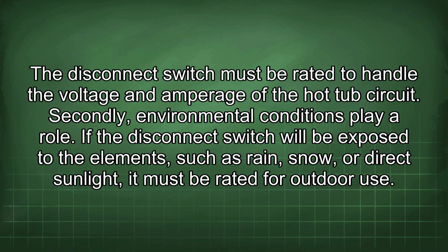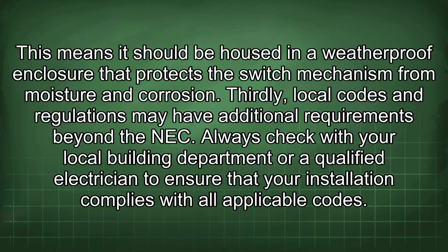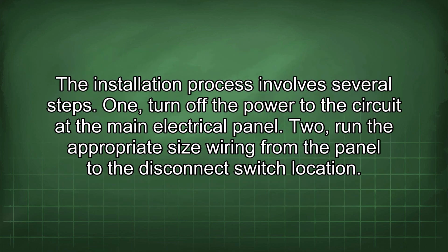Secondly, environmental conditions play a role. If the disconnect switch will be exposed to the elements such as rain, snow, or direct sunlight, it must be rated for outdoor use. This means it should be housed in a weatherproof enclosure that protects the switch mechanism from moisture and corrosion. Thirdly, local codes and regulations may have additional requirements beyond the NEC. Always check with your local building department or a qualified electrician to ensure that your installation complies with all applicable codes.